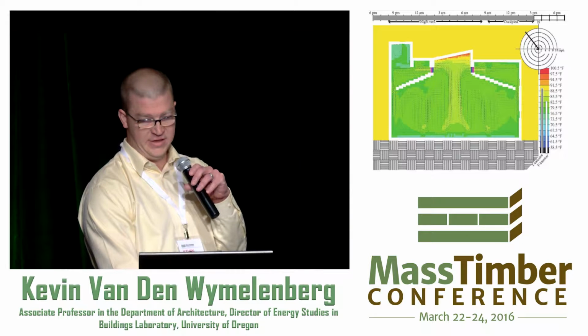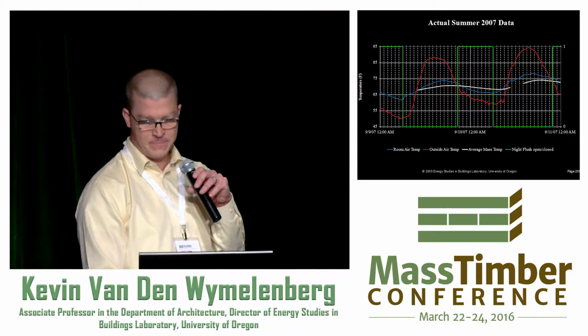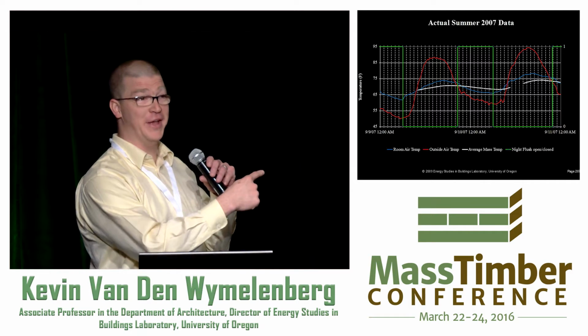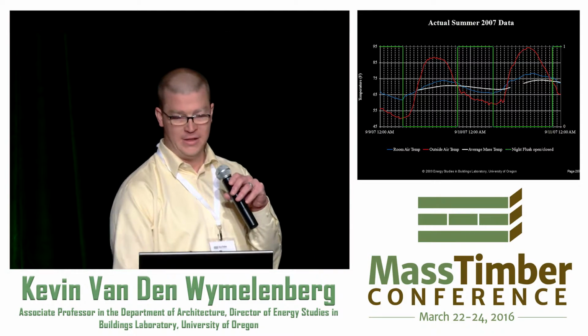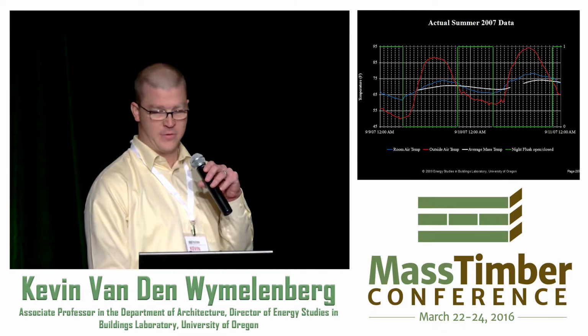So this is our goal, and then of course we start it all over again the next day. You can see some of the people in the room are creating these little plumes of heat, and then it goes to unoccupied mode. Those are real data from a course of a day. You just have to trust me. It's working. The good news is that this internal mass temp is not drifting up, and the outdoor temp is swinging wildly, but the indoor ambient air and perceived comfort are in the comfort range.